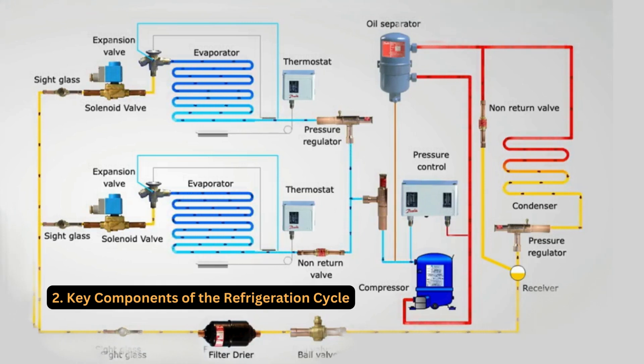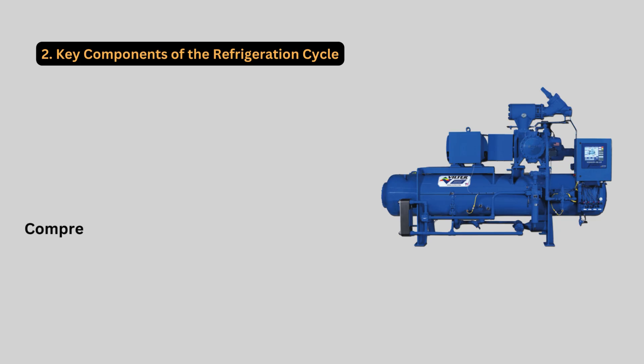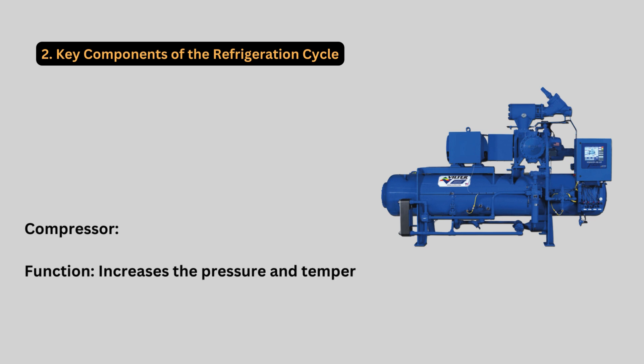Key components of the refrigeration cycle. Compressor. Function: increases the pressure and temperature of the refrigerant vapor. Types: reciprocating, screw, centrifugal. Principle: compresses refrigerant, converting it from a low-pressure gas to a high-pressure gas.